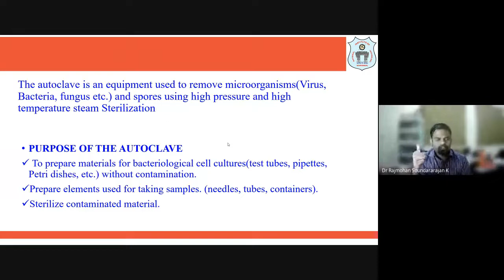So how does the autoclave work? Liquid water cannot be heated above 100 degrees Celsius in an open vessel, right? But when water is heated in a sealed vessel, there will be a pressure rise, so there will be a rise in the boiling point. For about 15 pounds of pressure per square inch, the temperature rises to 121 degrees Celsius. So for 20 minutes, at least if it is a 20 minute operation, we want to maintain the same temperature and pressure, 121 degrees Celsius and 15 psi. That needs to be maintained during this operation.